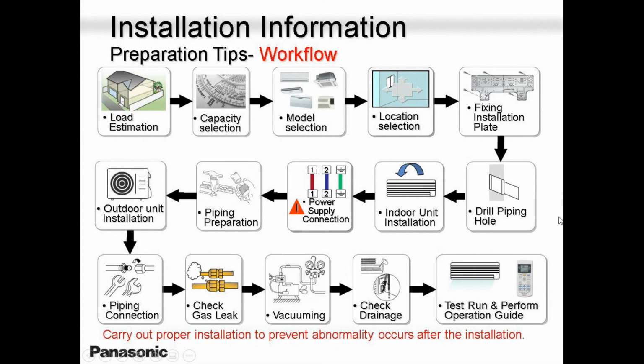So basically, you will go into a home when you get a call. You will do your load calculation, please. Then you will pick a model. Once you pick a model, you will look for a good location. This is very important, guys. Pick a very good location so that the homeowner doesn't get any cold draft or hot air blowing straight on the person's head or body. So please try and get the correct location.